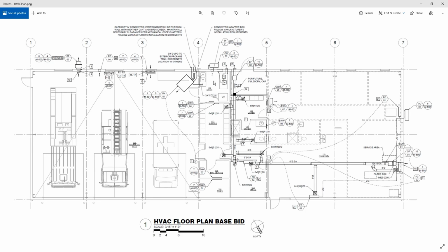We didn't do any balancing of airflow for this room, so this exhaust fan is actually probably not exhausting its full design capacity. It's probably only exhausting the infiltration rate of the room, which is probably fairly minimal. So what we need to do is balance that exhaust fan with the infiltration rate.